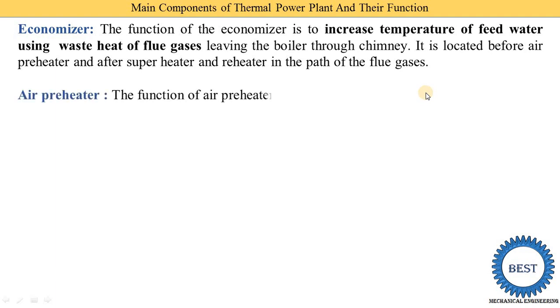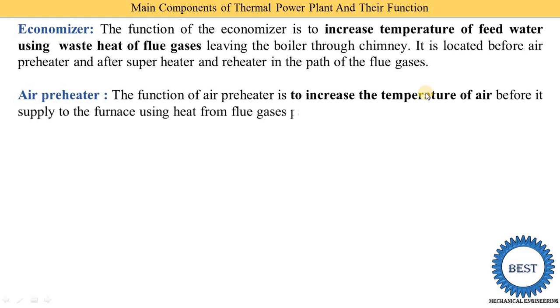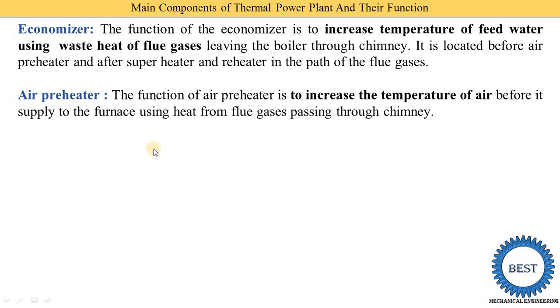The fourth heat exchanger used with the boiler is the air preheater. From the name you can understand it is used to heat the air before it is supplied to the boiler for combustion — that's why it is called the air preheater. The function of the air preheater is to increase the temperature of air before it is supplied to the furnace, using the heat from the flue gases passing through the chimney.